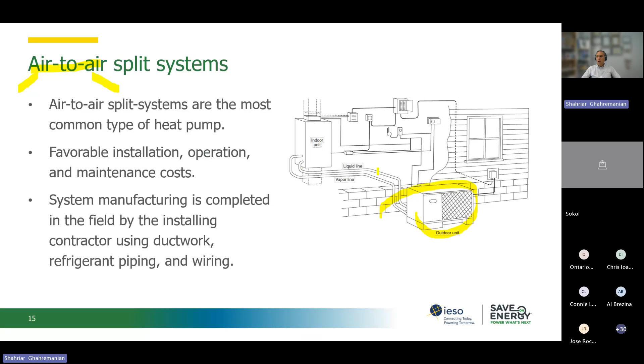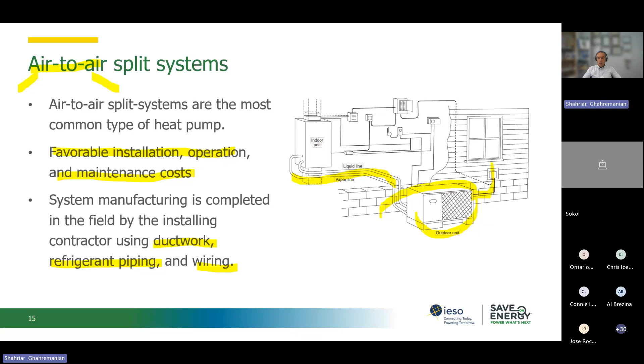And then that's it. This outdoor unit can provide us heating during the winter season and cooling during the summer season. So when we want to install it, we need to do the duct work because it's air inside. And we also need to bring the refrigerant piping and do some electrical wiring. So this has a favorable installation, operation, and maintenance cost. That's why everybody prefers to have these air-to-air split systems. In the air-to-air split system, as I showed you in that slide for heating and cooling, we have a heat exchanger coil, a compressor, and a fan and motor. The other difference is that the fan or motor is not on the top, it can be on the sides of the heat pump.